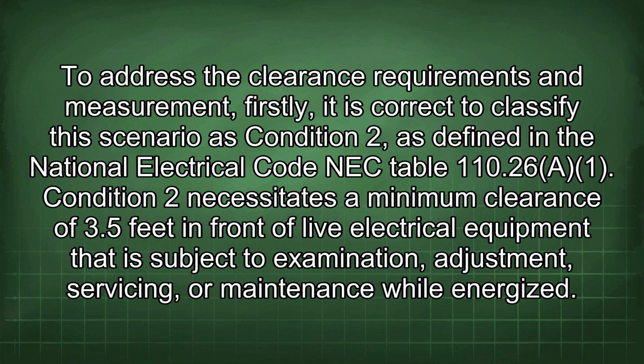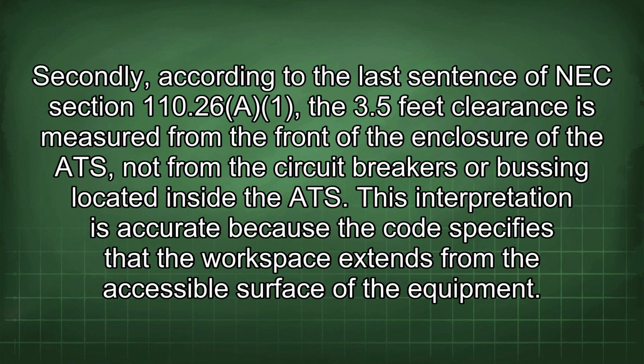Condition 2 necessitates a minimum clearance of 3.5 feet in front of live electrical equipment that is subject to examination, adjustment, servicing, or maintenance while energized. Secondly, according to the last sentence of NEC Section 110.26(A)(1), the 3.5 feet clearance is measured from the front of the enclosure of the ATS, not from the circuit breakers or busing located inside the ATS. This interpretation is accurate because the code specifies that the workspace extends from the accessible surface of the equipment.